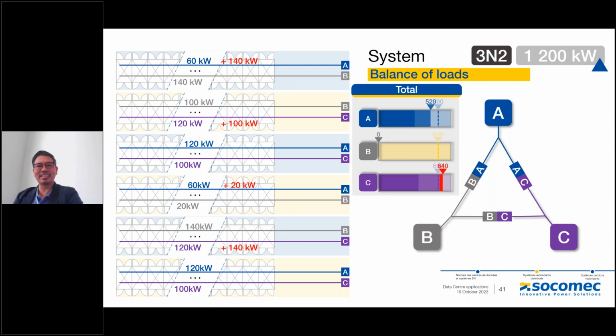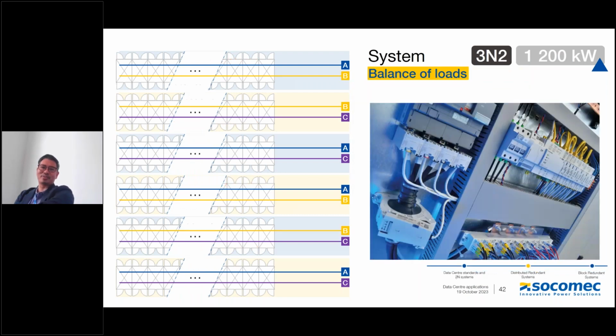Balancing is the key to maintaining balance in your electrical system, and this can be achieved in different ways. If you're familiar with monitoring systems, you can use one. You can set thresholds for your IT engineers, customers, or operators to make sure they plug into the right device, and it sends alarms if you've reached the highest threshold you've set. So a DCIM or an energy management system will play a big role in balancing.